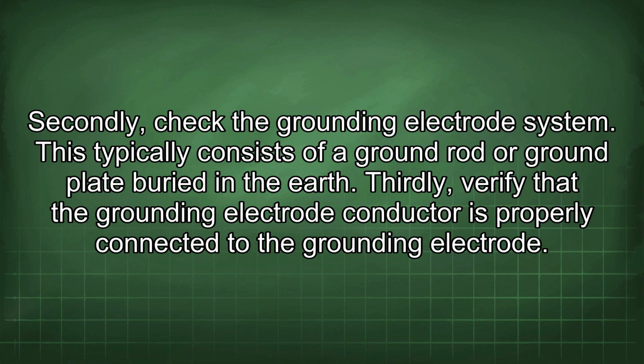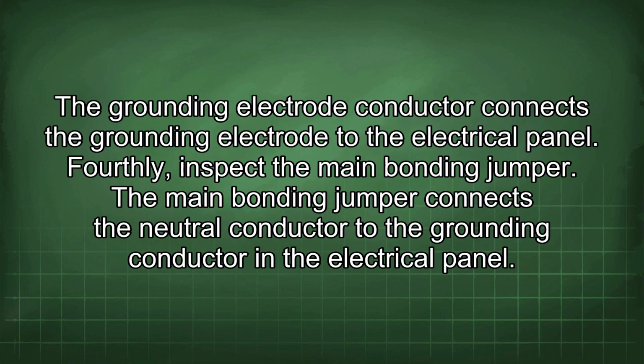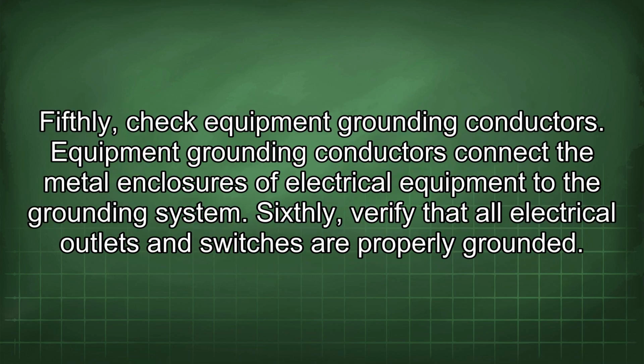Thirdly, verify that the grounding electrode conductor is properly connected to the grounding electrode. The grounding electrode conductor connects the grounding electrode to the electrical panel. Fourthly, inspect the main bonding jumper. The main bonding jumper connects the neutral conductor to the grounding conductor in the electrical panel. Fifthly, check equipment grounding conductors. Equipment grounding conductors connect the metal enclosures of electrical equipment to the grounding system.